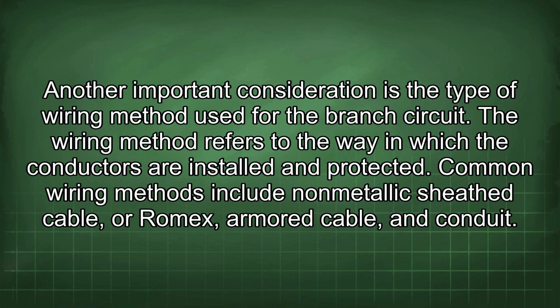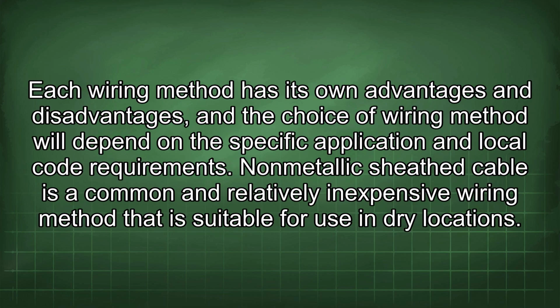Another important consideration is the type of wiring method used for the branch circuit. The wiring method refers to the way in which the conductors are installed and protected. Common wiring methods include non-metallic sheathed cable, or Romex, armored cable, and conduit. Each wiring method has its own advantages and disadvantages, and the choice of wiring method will depend on the specific application and local code requirements.